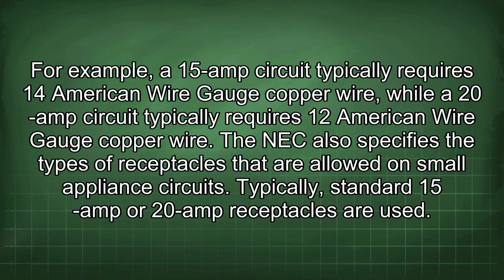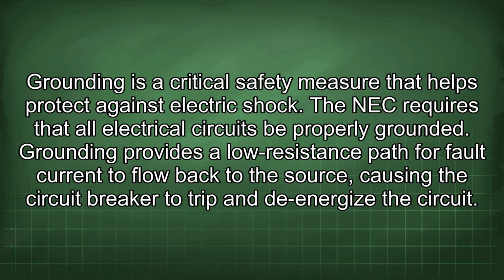The NEC also specifies the types of receptacles that are allowed on small appliance circuits. Typically, standard 15 amp or 20 amp receptacles are used. Grounding is a critical safety measure that helps protect against electric shock. The NEC requires that all electrical circuits be properly grounded. Grounding provides a low resistance path for fault current to flow back to the source, causing the circuit breaker to trip and de-energize the circuit.